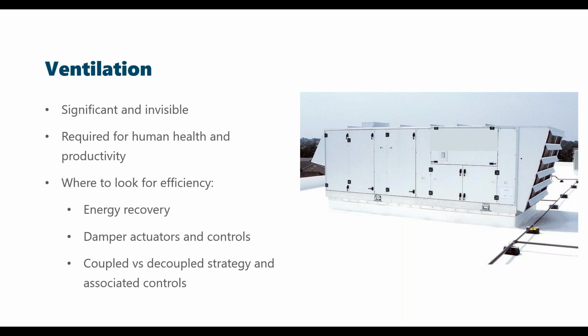Dampers and actuators and controls, again, we don't need to be controls technicians to be able to look quickly and understand if damper actuators are never modulating, or if it makes sense given the occupancy and the outdoor air conditions. Is that outdoor air damper in the position that makes sense that you assumed it would be in? The coupled versus decoupled strategy and the associated controls, that's something I like to just understand and talk through with my customers.